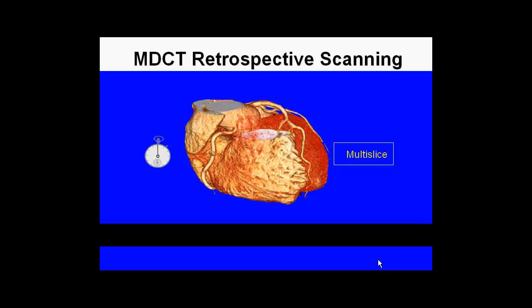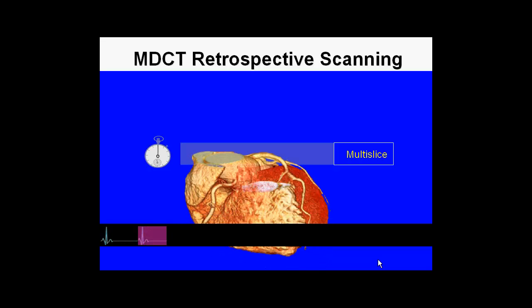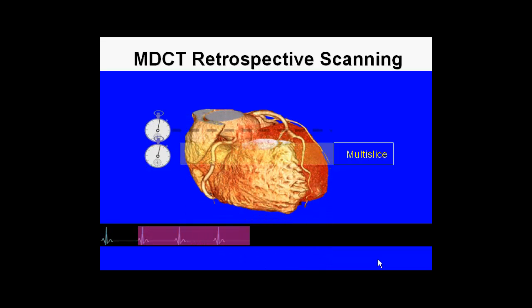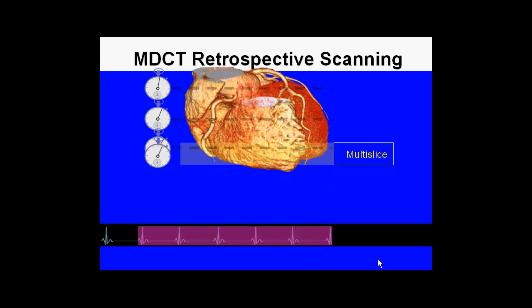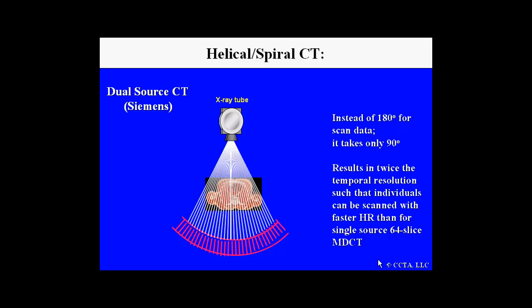This is an overview of the timing of performing multi-detector retrospective scanning using a 64-slice scanner. Images are acquired in an individual band, which represents the z-axis coverage of each of the 64 detectors. A single-source scanner can acquire images as noted, however it still requires at least 180 degrees of scan arc to acquire a single set of images.